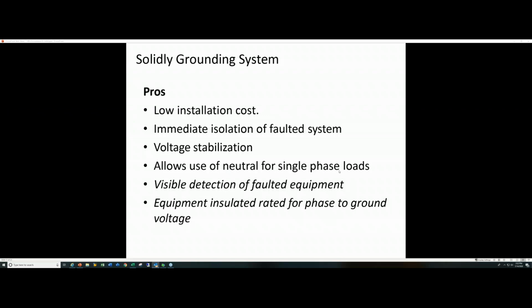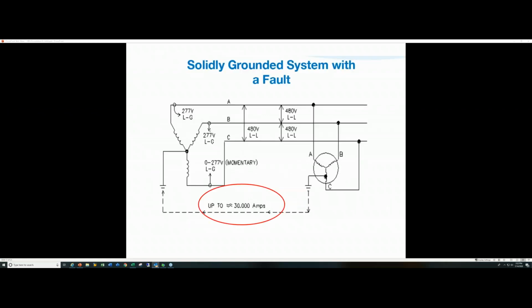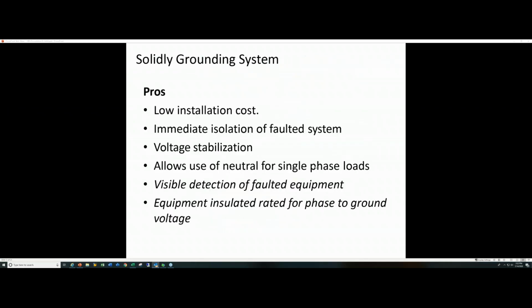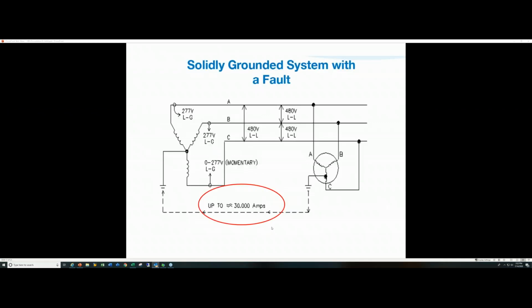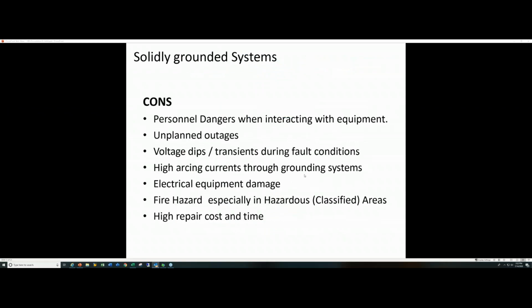It allows the use of a neutral for single phase loads. So if you were wanting to take this into a transformer, yeah, sure, you could have your neutral to line loads, your single phase loads. There's definitely a visible detection of your equipment. Where is it faulted? Well, there it is. It's burnt up. You can see that right away. And the equipment insulating rating, phase to ground voltage, is based upon the phase to ground, which in that particular case that I just showed you, the 277 rating, okay?